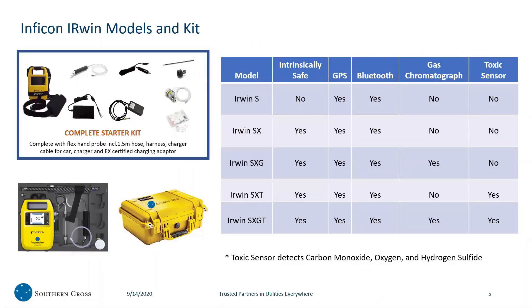There are five versions of the machine. The S is the base model — it is not intrinsically safe, but it does have GPS and Bluetooth, which is available with all the machines. All machines with an X are intrinsically safe. The machines with a G include the gas chromatograph, and the machines with a T include toxic sensors that detect carbon monoxide, oxygen, and hydrogen sulfide. The complete kit includes the harness, hand probe, fast charger for the car, staff and bell probe, regulator for your gas tank for calibration, your filter set, and charging cables.